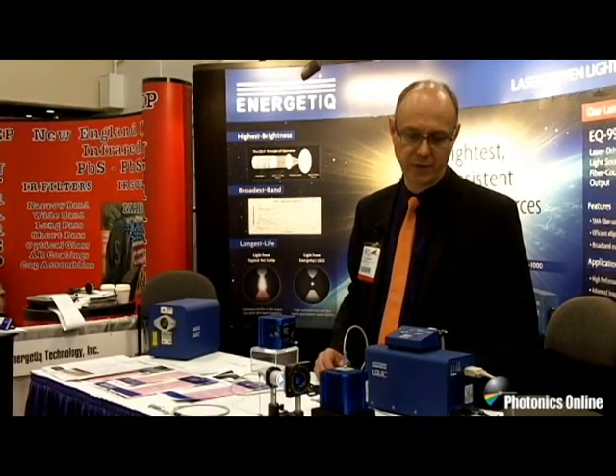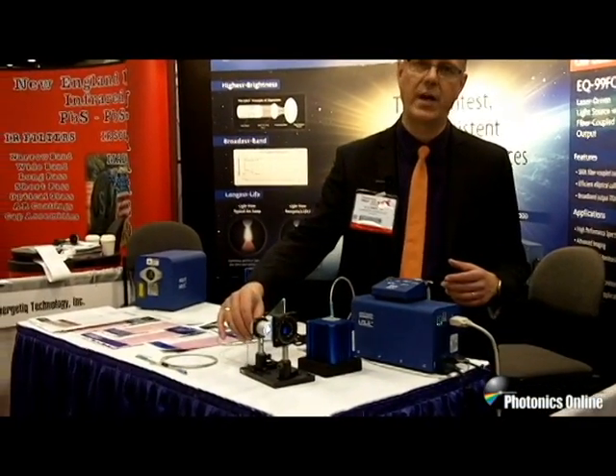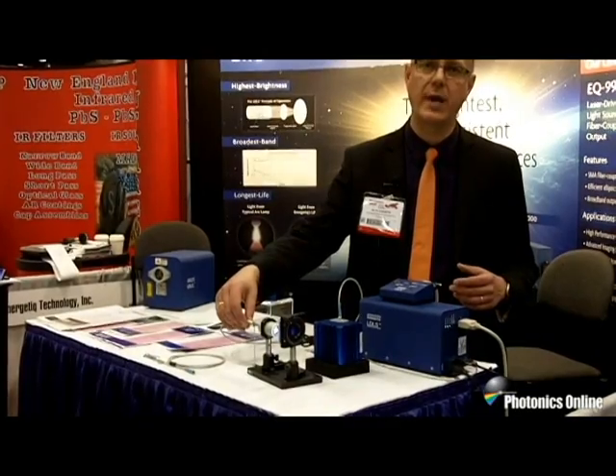We have units in our laboratory that have operated for more than 10,000 hours of lifetime, so we don't expect that the customers will have to change the bulbs very frequently. There are three different versions of the product. The laser-driven light source with the fiber coupling delivers the light into a very small diameter — in this case a 200 micron diameter fiber.